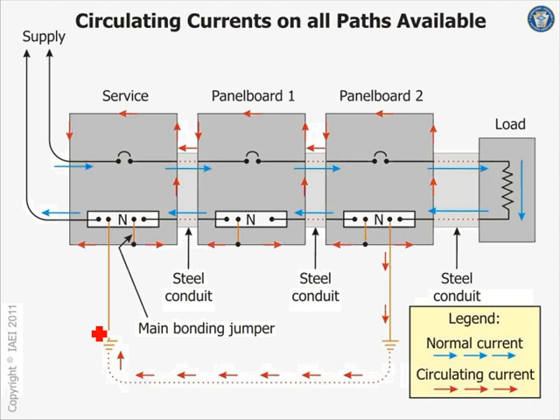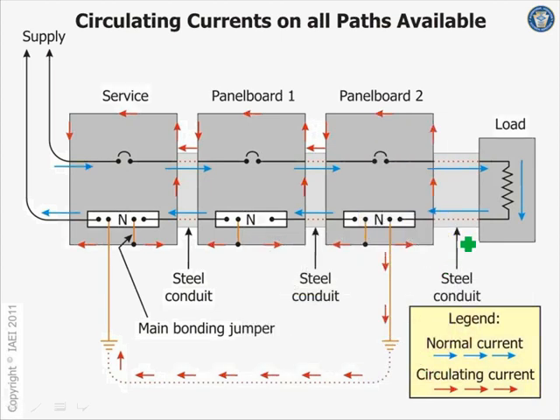But you still have an equipment grounding conductor going to your server. So if I have my green wire coming in here to my server, that's the equipment grounding conductor right here, tied to the frame of that server, completely isolated from the neutral.